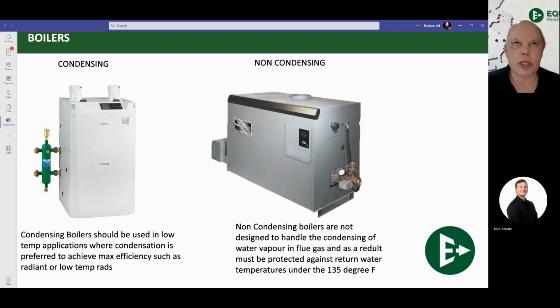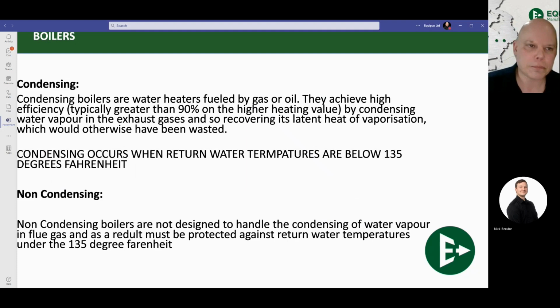Now, times are changing and we're using much larger rads and much larger heating coils in our air handlers. That'll give you more BTU output at lower temperatures. But a good way to think about it is what is happening today versus what is going to happen tomorrow. Right now, to get those sorts of systems to give the same output at lower temperatures, they need to be much larger and much more expensive. Maybe they can't do that. That's where non-condensing would make sense. But again, you're only going to really find non-condensing available now in commercial applications. Condensing is most of your home applications.